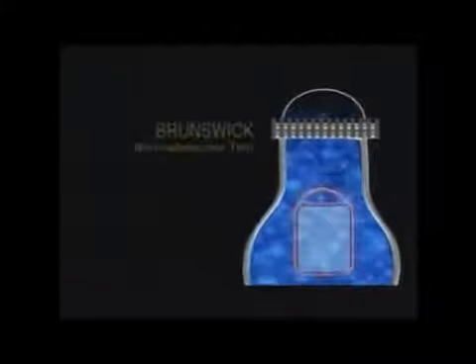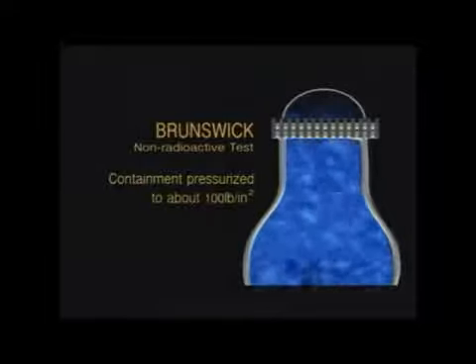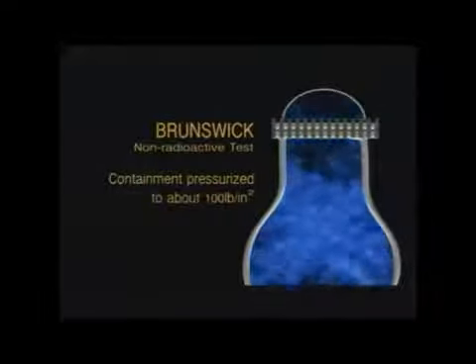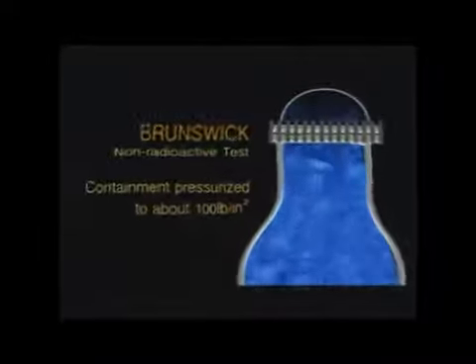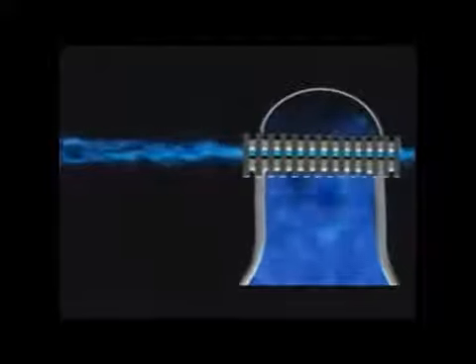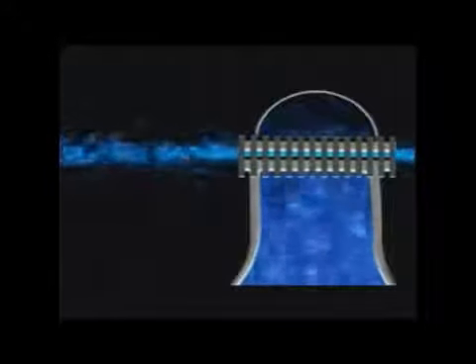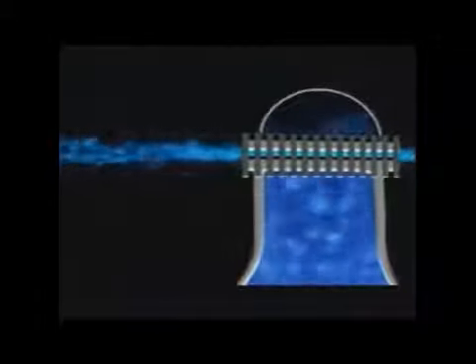When a containment was pressurized, it was pressurized to just about 100 pounds, and then something really strange and unexpected happened. The top, the head of the containment, began to lift off of the bottom of the containment. Getting back to my mug here, what happened was that the bolts that hold the top to the bottom began to stretch. And the top lifted and allowed the gases to slide out. That held the pressure in here at 100 pounds, even though gases were being pumped in.